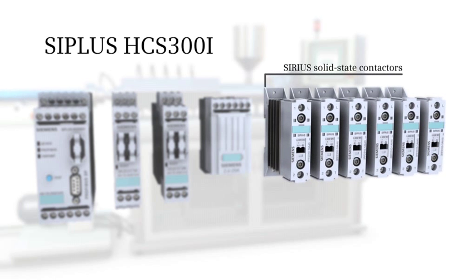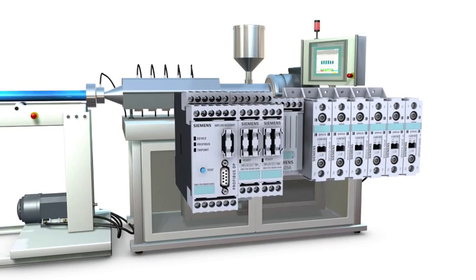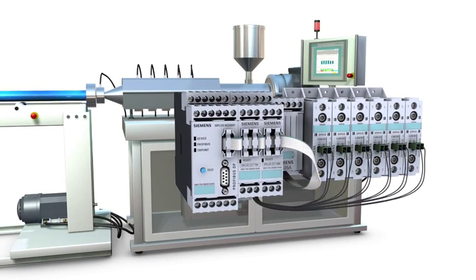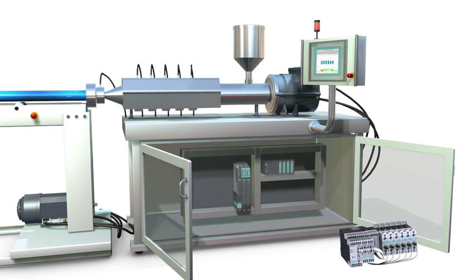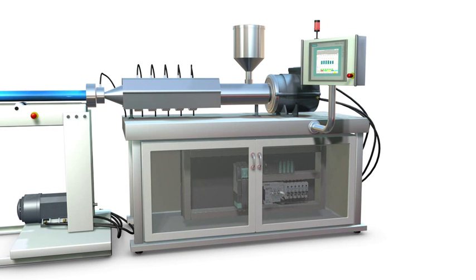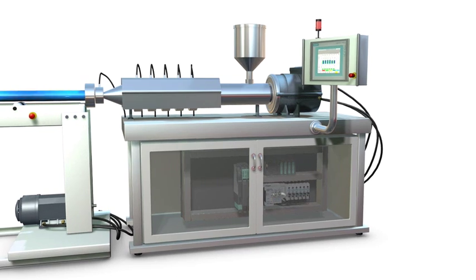The individual heater bands are switched by SIRIUS solid-state contactors, which can be protected by means of reasonably priced B-type circuit breakers. The solution is supplemented by the TCP3000 temperature control software, which runs on a high-level SIMATIC control system.